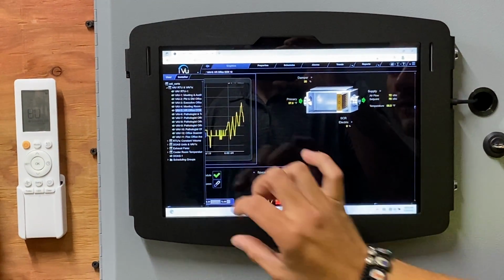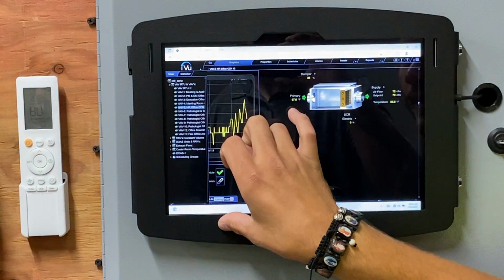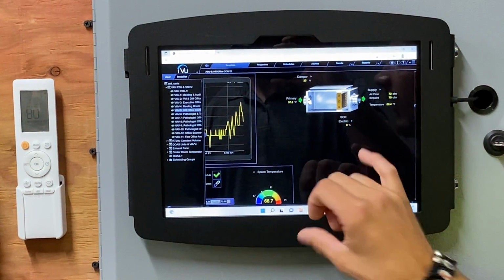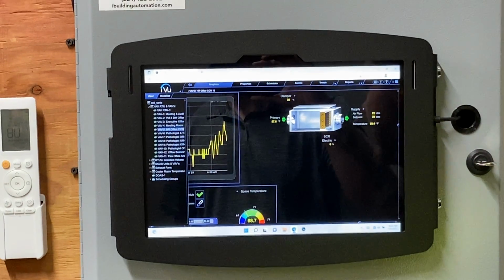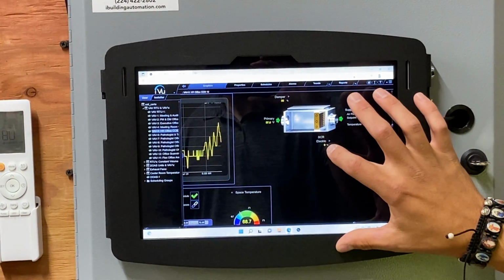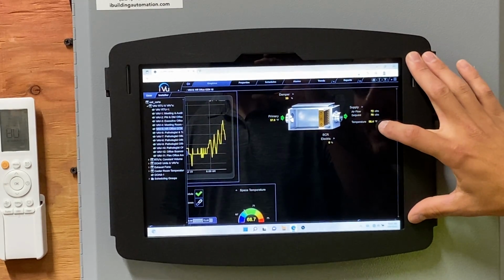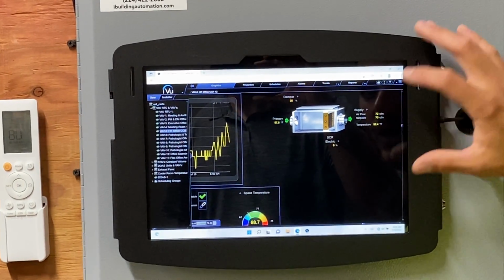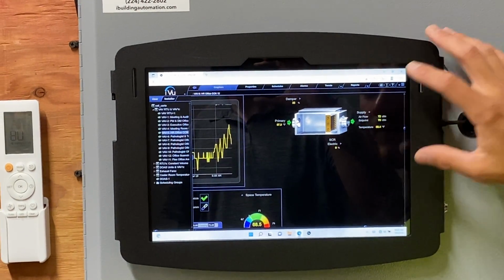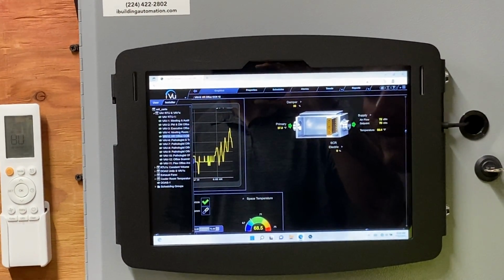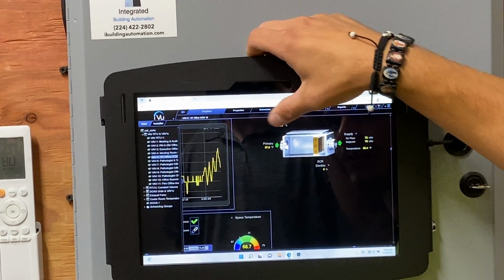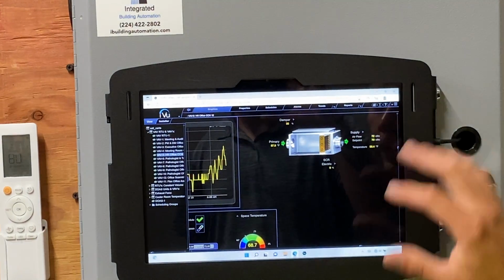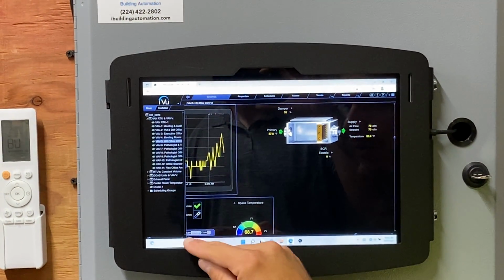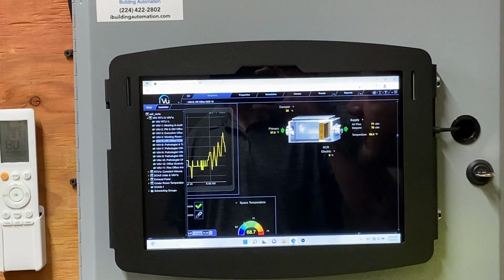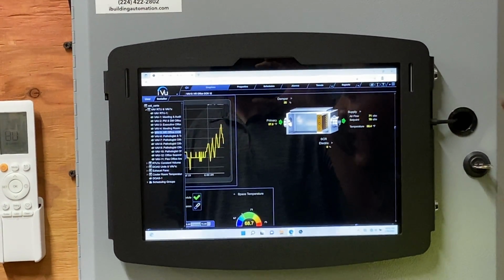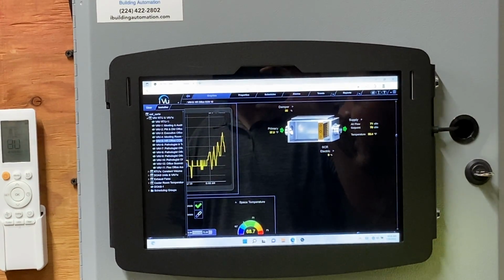this is going to show us our box now. So this is showing that we have 57 degree primary air, our SCR electric heat. All these boxes have ducted electric heat inside of them, where we have 0% on that, and then we have 58 degrees coming out. And we have a set point value right now of 70 CFM, and we're actually getting 72. And then you have your damper position here, which is 35%, showing what your box is. We've opened to a minimum percentage now because we are at 68, which is right at our threshold. So we're not going to push to maximum cooling or anything like that. So we're just in a terminal fan mode right now.